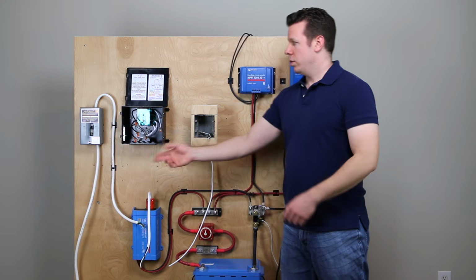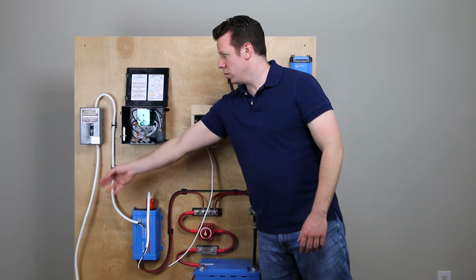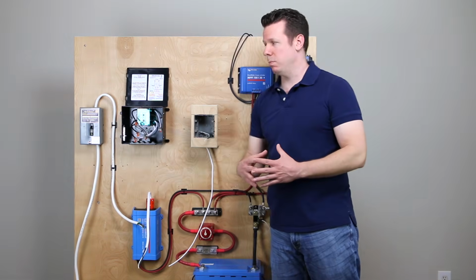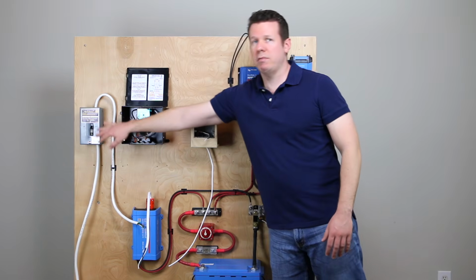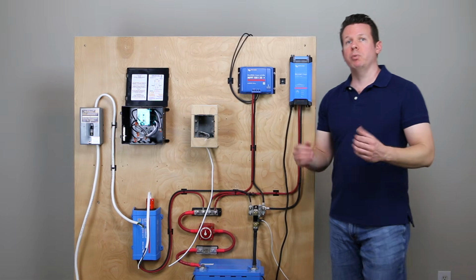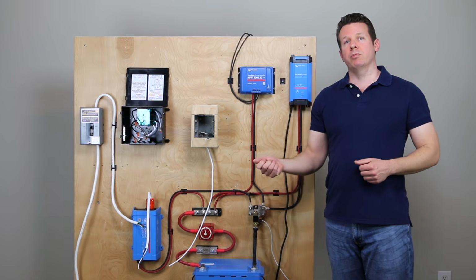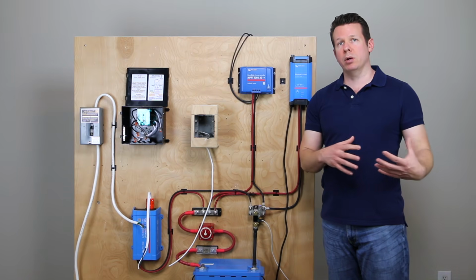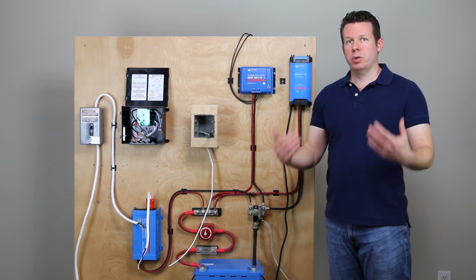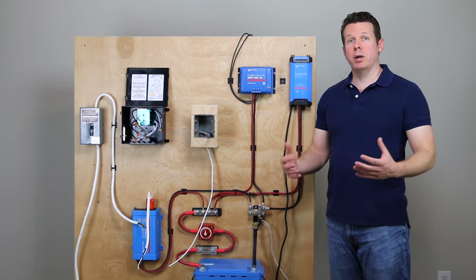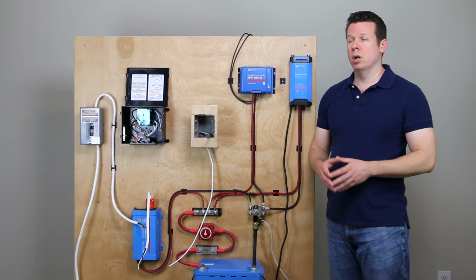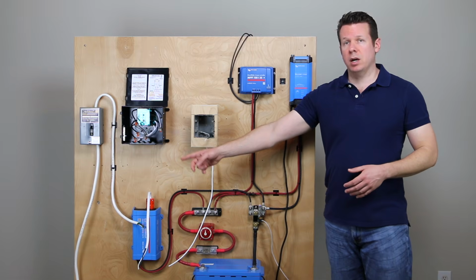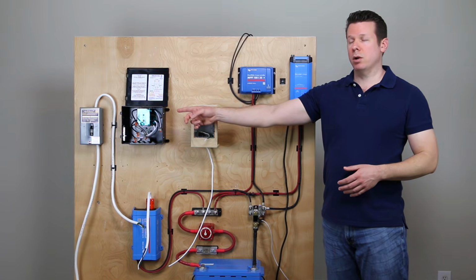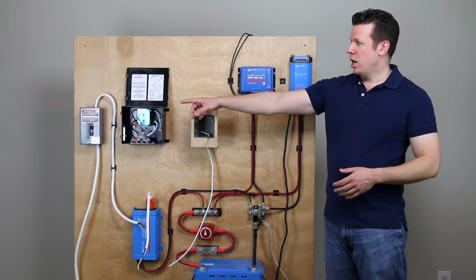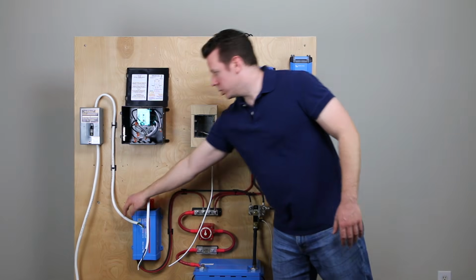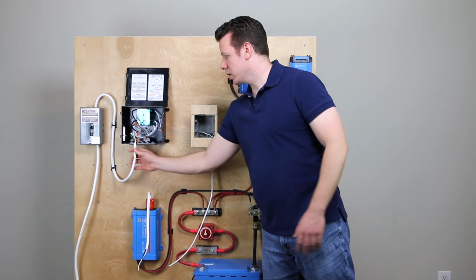For example, on the 30 amp shore power service here, we're using a 10 gauge cable, and I have an extra breaker. When you plug into the power grid, that receptacle will already have a breaker, but for extra safety, I often run the incoming line through an additional 30 amp breaker, again with 10 gauge cable, and that line comes up and ties into our transfer switch.